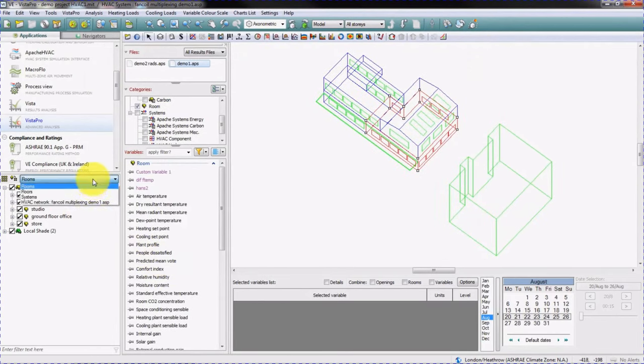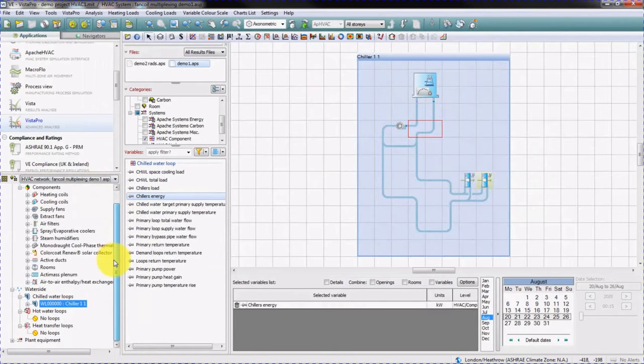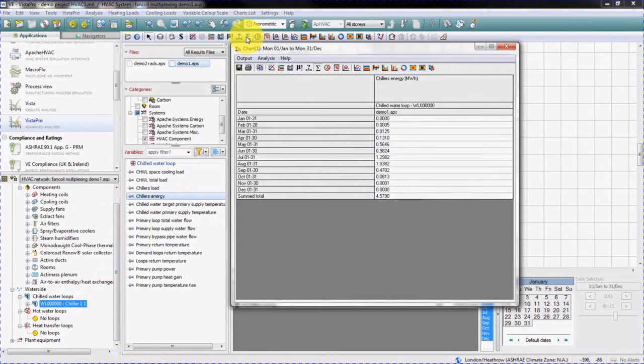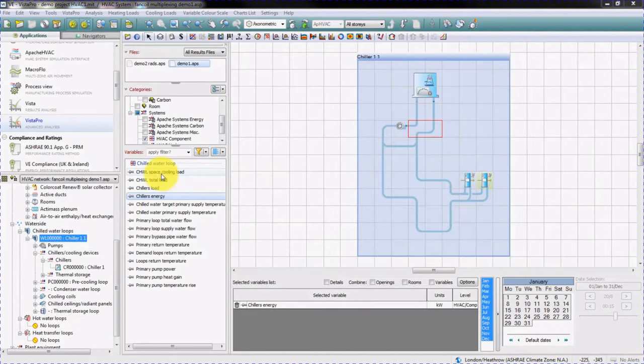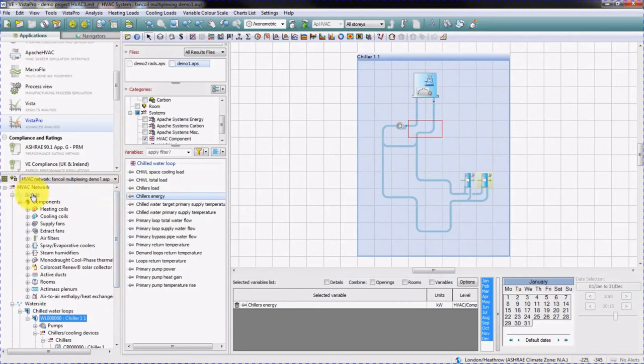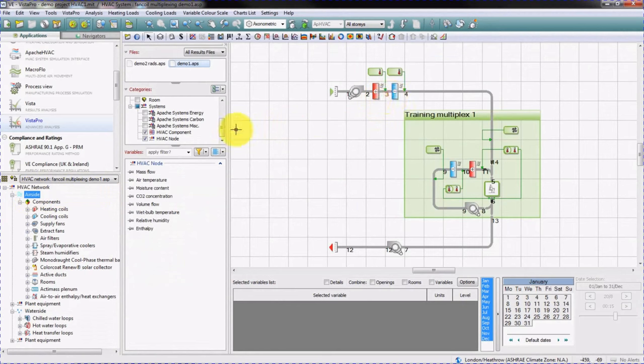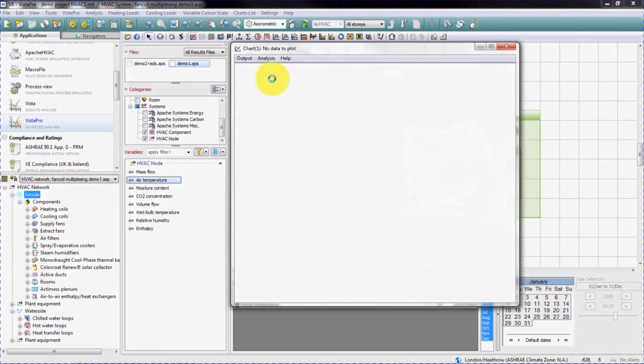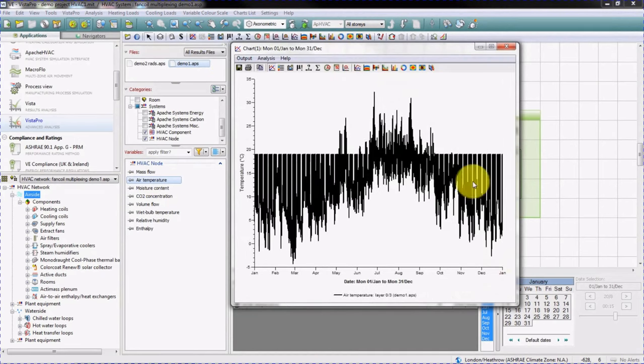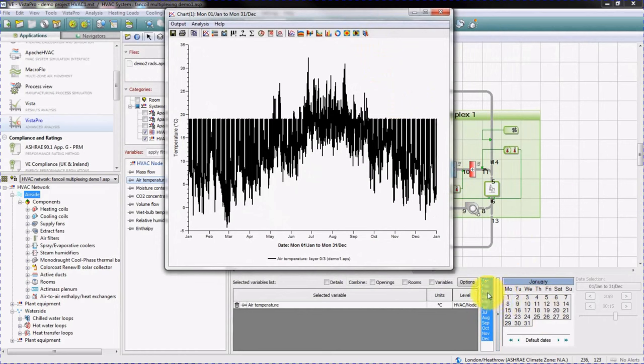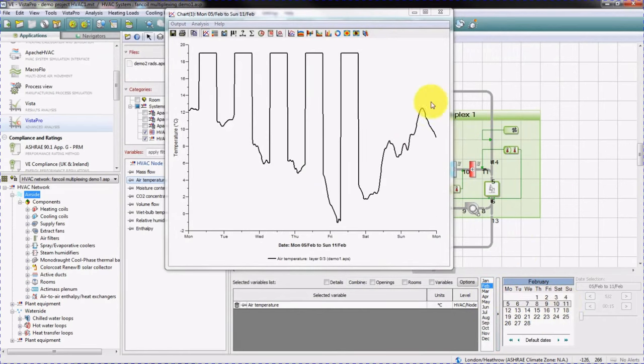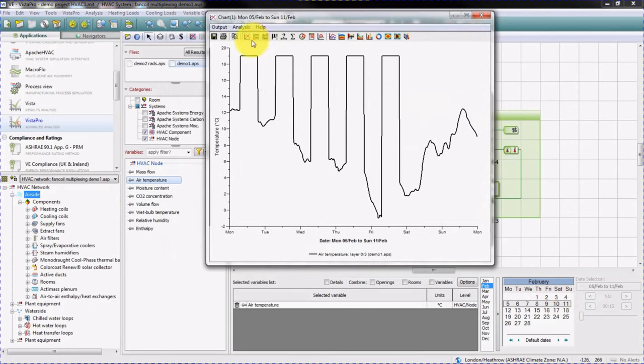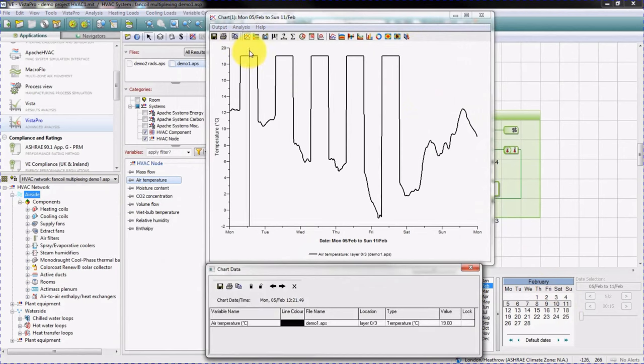In Vista Pro, you can interrogate the performance of the HVAC system including its components. For example, we can look at the chiller's energy consumption for the whole year. You can also interrogate the conditions at any point in the HVAC network. For example, at node 3, you can interrogate the air temperature or the mass flow rates. We'll look at the air temperature at node 3 downstream of the heating coil in February. This is very useful if you need to do some troubleshooting.